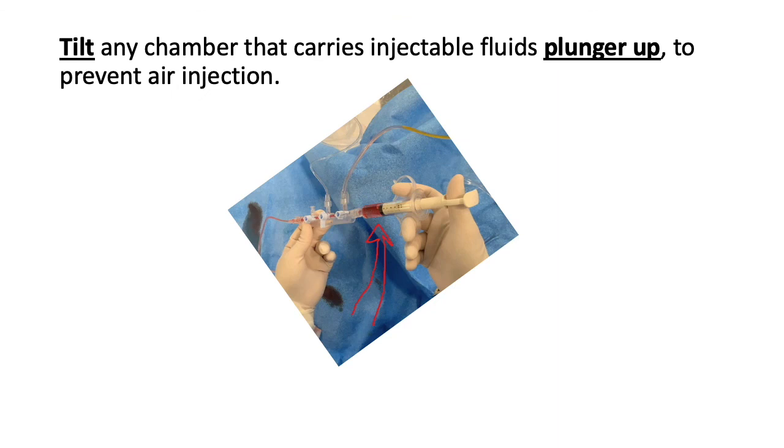A very important rule is to tilt any chamber that carries injectable fluids plunger side up so as to prevent air injection.